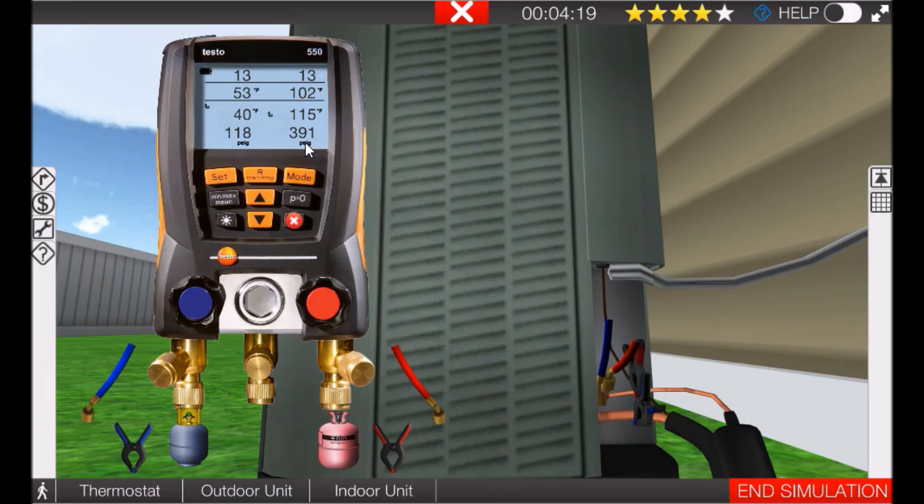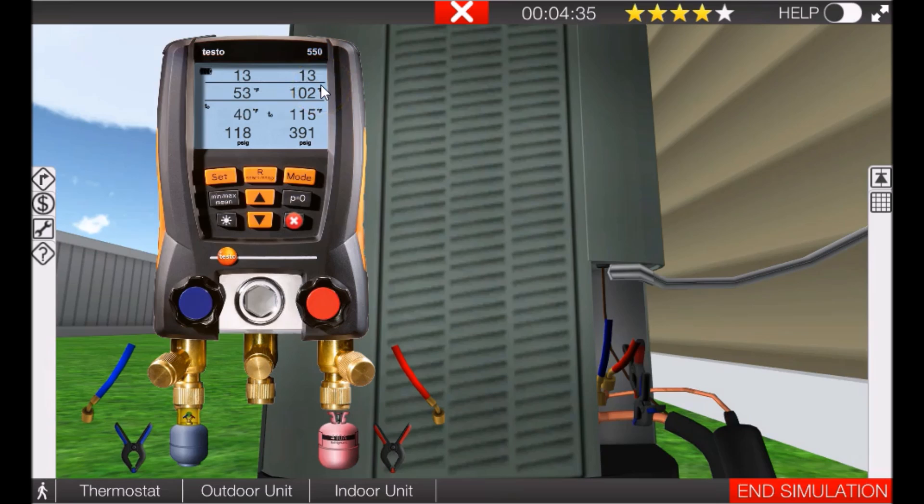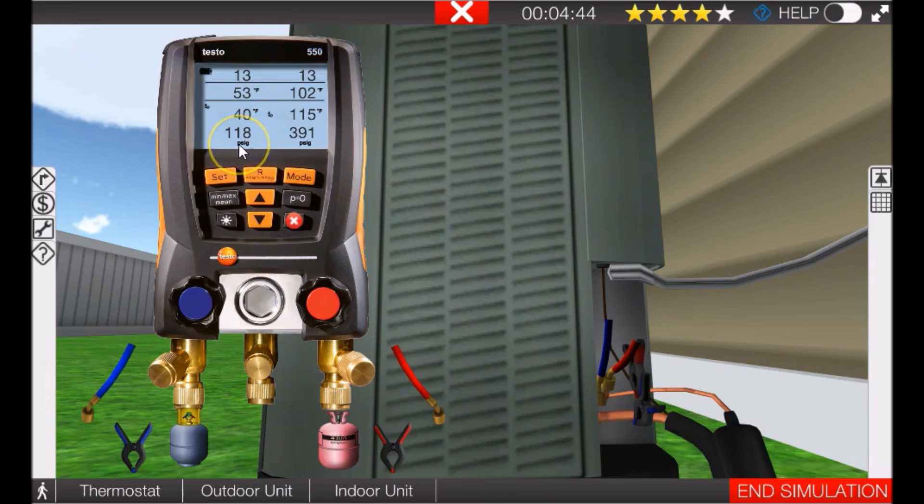So 391 psig - it was 351. 115 degrees Fahrenheit on the discharge line - it was 108. It's now 102 degrees Fahrenheit on the discharge line - it was 103. And we have now 13 degrees of subcooling, which is a much better subcooling number than the 5 degrees. So now our subcooling is good.